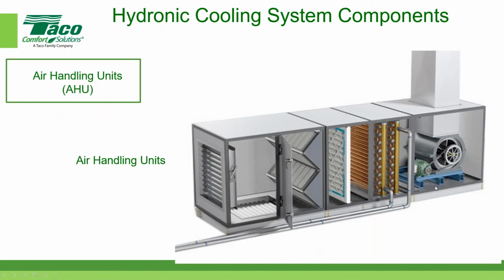You would send chilled water to an air handling unit, and they can be either roof mounted or they can be inside mechanical rooms. But basically, we're sending chilled water. The chilled water flows through a coil. And in this case, the air is entering this unit from the left, passing through the filter sections and then into the cooling coil, and then the fan blows the air out. It could blow the air up. The fan could be oriented to blow the air horizontally or vertically down. It all depends on the orientation of the fan and how the air handling unit is designed. So that's another device.